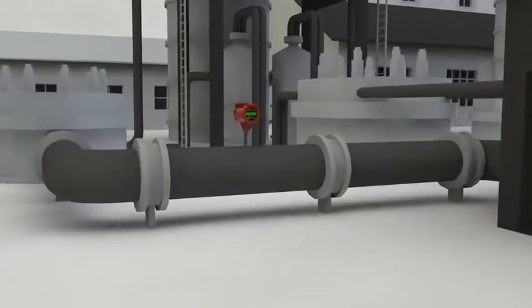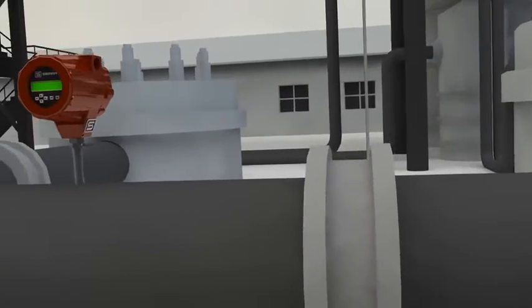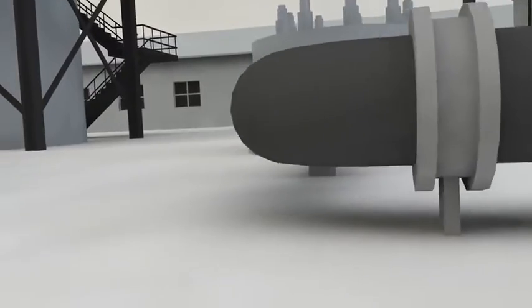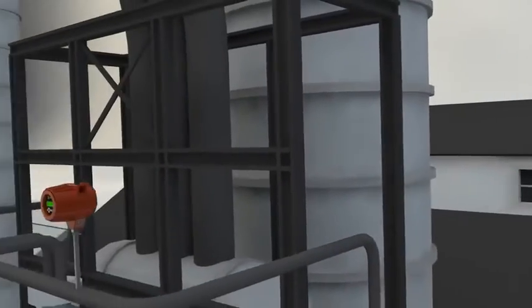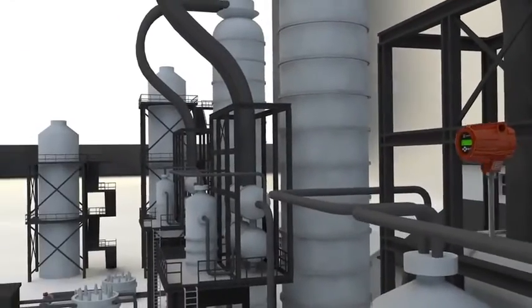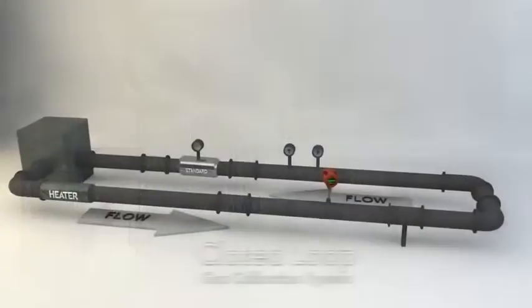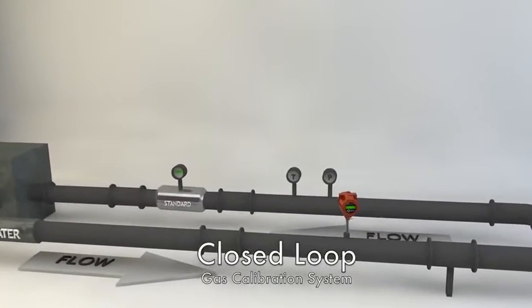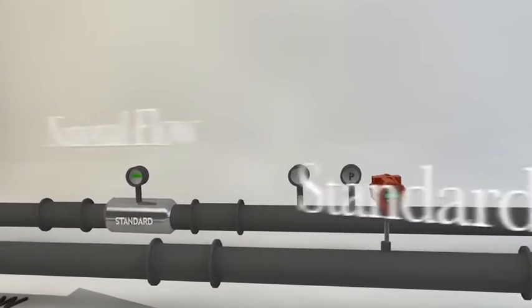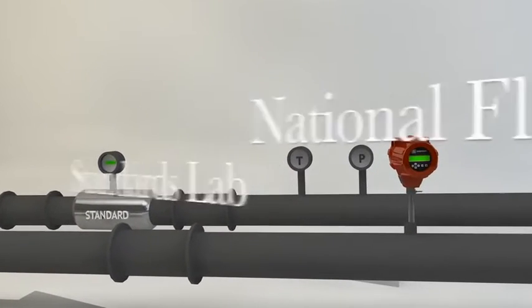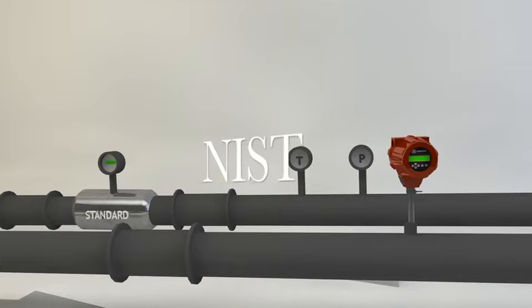So, with this in mind, what is the purpose of a flow meter? This is an important question to think about. The purpose of a flow meter is to transfer an accurate calibration to the field. As a result, a flow meter is only as good as its calibration. Thermal mass flow meter manufacturers must assure that the instrument is calibrated on a closed-loop gas calibration system that is traceable to a national standards laboratory, such as NIST for the United States.